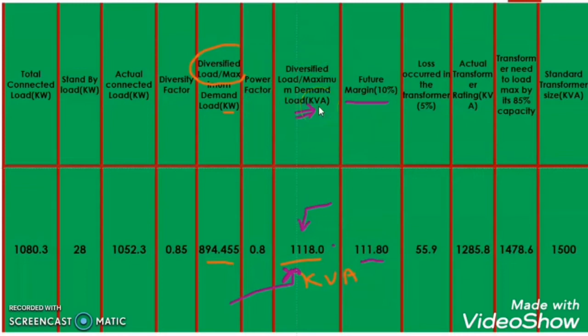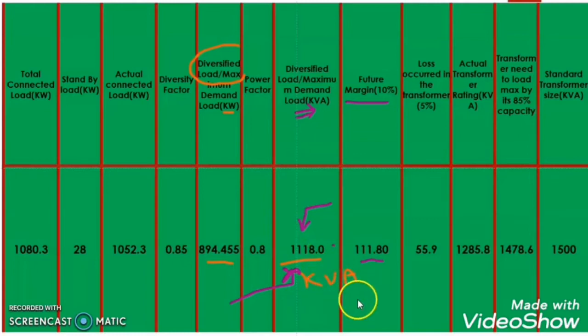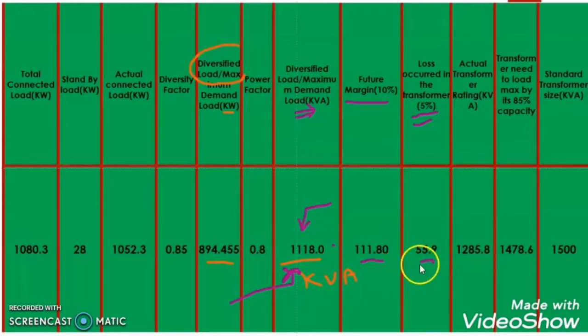The transformer is not always 100% efficient — there will always be some losses in the transformer, and those losses are also a load on the transformer. If we select a transformer of the same rating as the load, then due to transformer losses, it cannot process that full load. So we must always consider a losses margin while selecting the proper transformer size. Here I selected the transformer losses as 5%, which is 55.9 kVA.